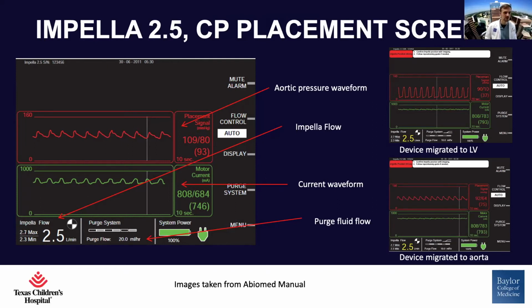However, that should be primarily used in the setting of a cath lab and in a very temporizing mode, mainly because the device is performing at its maximal capability and has a high risk of earlier failure or generation of hemolysis. Another important aspect of the screen is the flow of the purge system. It tells you how many cc's per hour are going into the patient for fluid calculations. The other essential parameter is the placement signal, which enables you to measure pressure directly within the aorta.